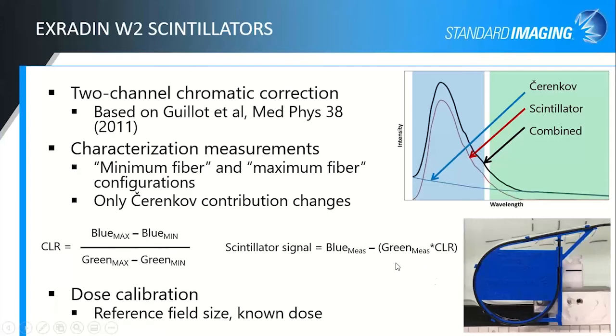And the idea here is that you're keeping the dose to the scintillator the same and changing only the Cherenkov contribution. Sorry, I should have put the equations up a little sooner. But we calculate this correction factor called the Cherenkov light ratio by taking the change in the blue signal divided by the change in the green channel signal. And this gives us a correction factor we can multiply by the green signal for any subsequent measurements to allow us to remove the Cherenkov from the blue signal.